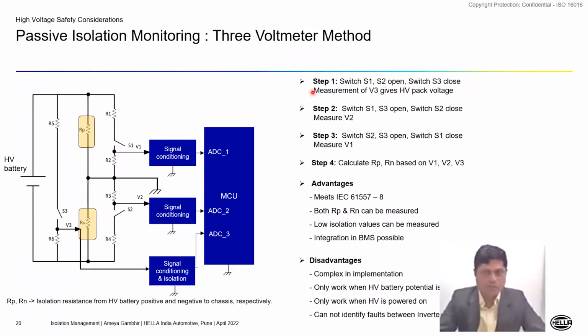So in the first step, switch S1 and S2 are open. This is the S1 switch, which is connecting R1 between HVDC positive and chassis, and S2 switch is connecting the HVDC negative and chassis through R3 and R4. So first we only close switch S3. Basically by closing the switch S3, we sample the line voltage at that instance. Then in the next step, we close the switch S2, and then we measure the voltage which is between HVDC negative to chassis.